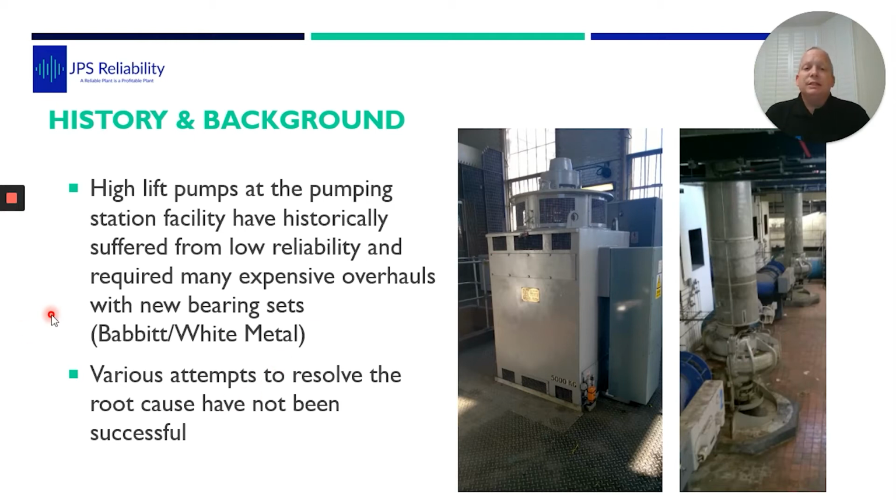They've been having random routine failures of these pumps. Lots of people come along to try and fix it. One thing we did see was that there wasn't enough record keeping of the failures, and when a failure happened, it was a panic to get it back up and running, so no one revisited it. Once it's fixed and it's running, forget about it, onto the next problem. The documentation of previous failures was limited.